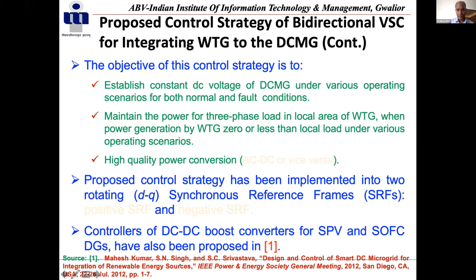The wind turbine capacity is 600 kilowatt at 690 volt. The SPV is 100 kilowatt, fuel cells is 100 kilowatt, and the peak power capacity here is 1 kilowatt. The transformer used for the wind turbine is 25% more than this capacity, and similarly for other directions, since the source here is giving 600 power, it is rated higher because of certain emergency rise conditions.